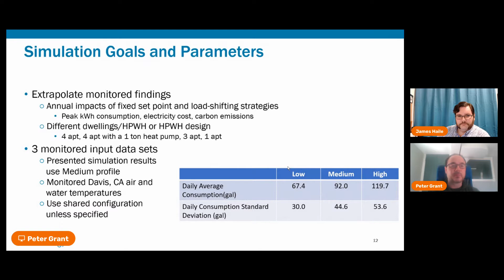And we looked at all of these different cases with 3 monitored input data sets. We chose 3 of the heat pump water heater profiles from the monitored data, one representing a low use case, one representing a medium use case, and a third representing a high use case. So we're both bounding the problem and looking at the average situation. And then when we were running these simulations, we also used the monitored air and water temperature data from the Creekside project. So these are all cases of things that happened in real buildings, and it's real data driving the simulation model, but it is a kind of targeted case. And so here I have some sample simulation results over the next couple of slides.